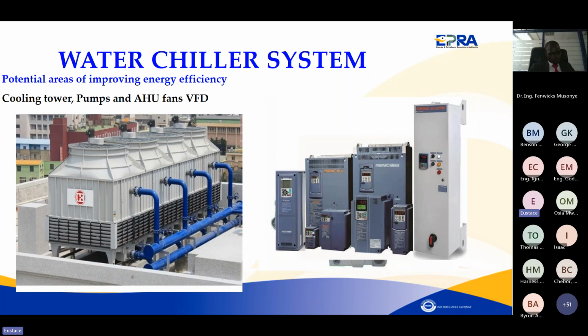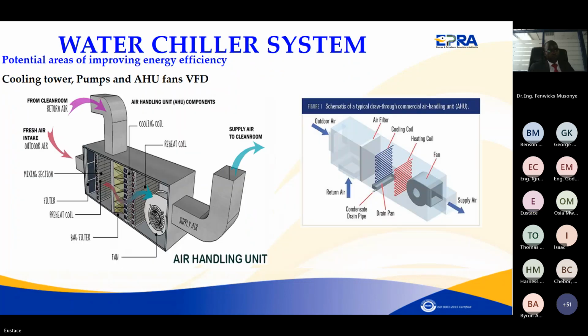You can use VSDs on the cooling tower fans, the pumps, the chillers, the AHU fans, and so on. But as I've said, you should be very careful when dealing with the AHU. Don't try to tamper with the AHU, especially in the data center. Before you tamper with the flow of the AHU fans, check the operations there. Can they be affected if the airflow is reduced? The VSDs, either in all those air handling units.